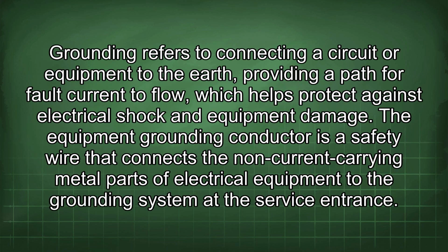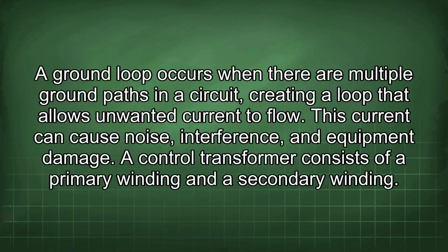Grounding refers to connecting a circuit or equipment to the earth, providing a path for fault current flow, which helps protect against electrical shock and equipment damage. The equipment grounding conductor is a safety wire that connects the non-current carrying metal parts of electrical equipment to the grounding system at the service entrance. A ground loop occurs when there are multiple ground paths in a circuit, creating a loop that allows unwanted current to flow. This current can cause noise, interference, and equipment damage.